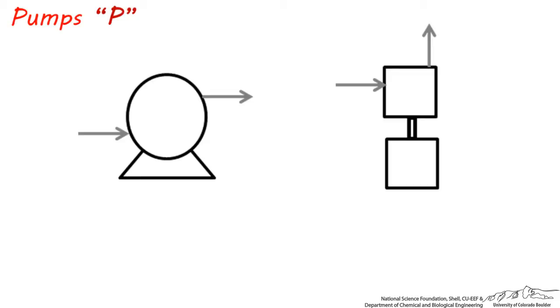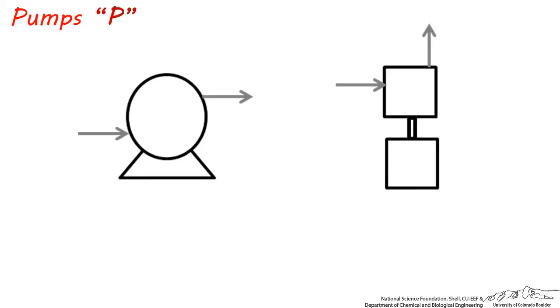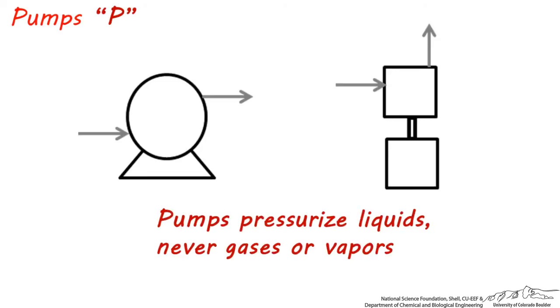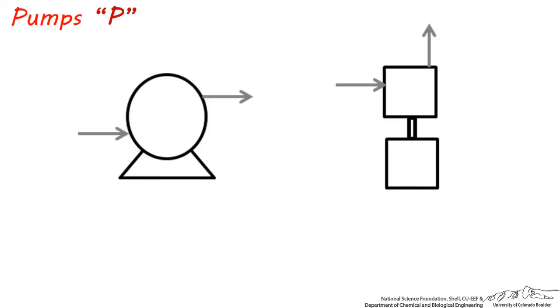These are all pumps, and they have the letter abbreviation P. This is the most common general symbol for a pump, and this is the representation of a pump with a spare. The job of a pump is to pressurize liquids. They should never be used to pressurize vapors, otherwise the pump will be damaged by cavitation. Remember that compressors are designed to pressurize vapor or gas.